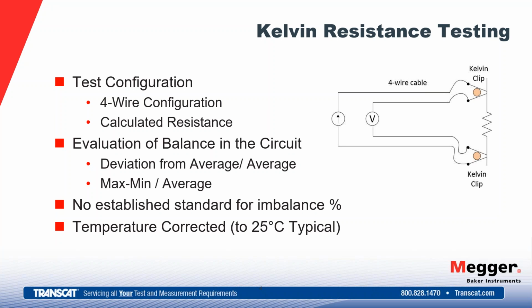So it's kind of hard to know, walking up to a motor, what the actual phase-to-phase resistance of that motor is. And if you're testing from switchgear, that's going to include the cables. The length of the cables plays into how much resistance is in that circuit, and you wouldn't necessarily know what that resistance should be. So the way we're going to evaluate this test is through the balance of each of the 3 phases. A way that we do that is to take it into 2 methods.